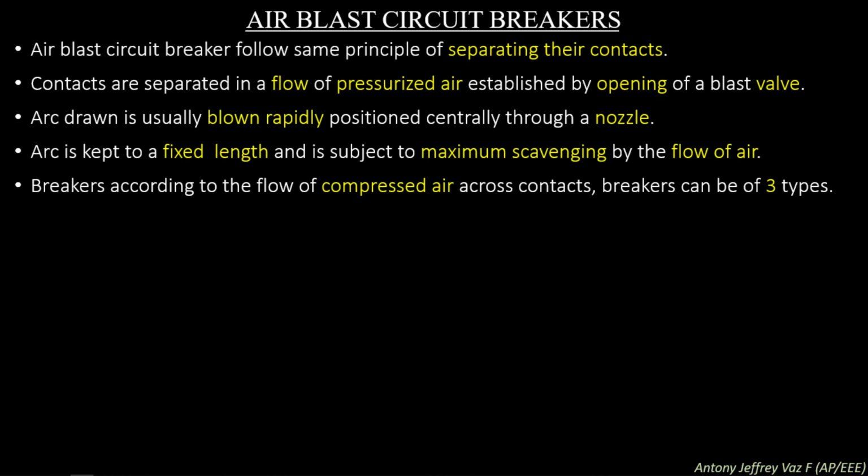Breakers, according to the flow of compressed air across the contact, can be classified into three types. Air blast circuit breakers use the principle of blowing high pressurized air in the path of the arc so that the arc can be easily extinguished and the contact space dielectric strength can be increased in a rapid manner.